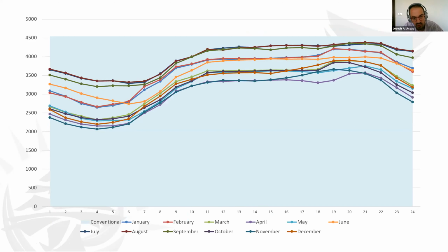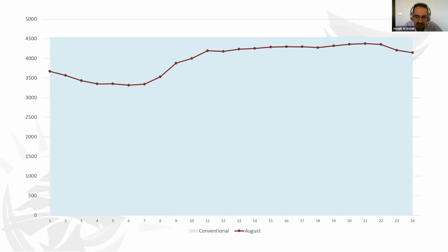Now, another point of view that is very interesting here, just to clarify, is that the previous idea means that we will need to invest 1,600 megawatts more to satisfy the need in December than in August or November. So in this case, this is the average day in August. If we look at the average day in August, in order to cover that demand we need around 4,550 megawatts, which is satisfied by the current plan. Now, the peak demand is around 4,300 megawatts, so this leaves us with a 200 megawatt unit of spinning reserve, which is within the international standards.